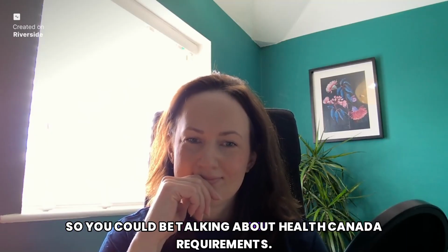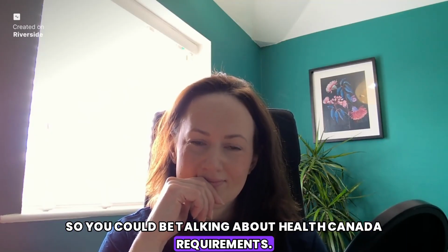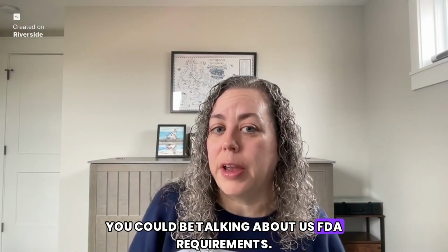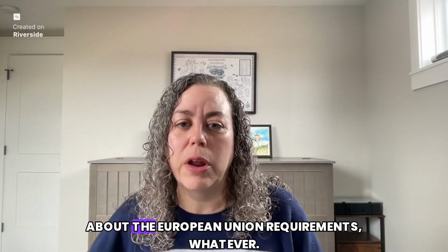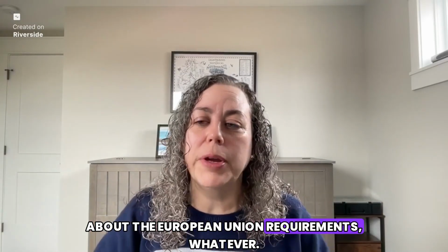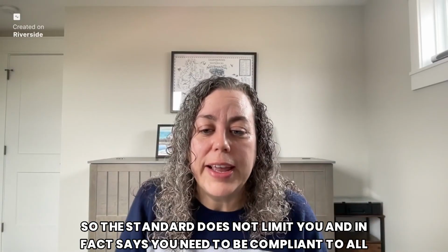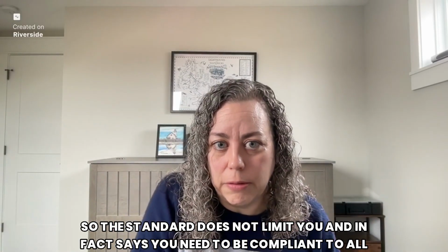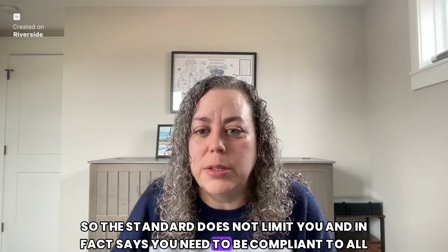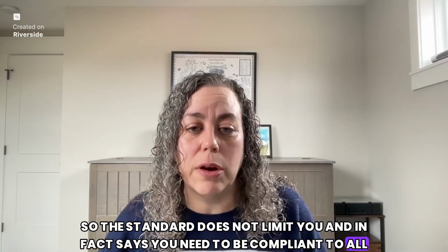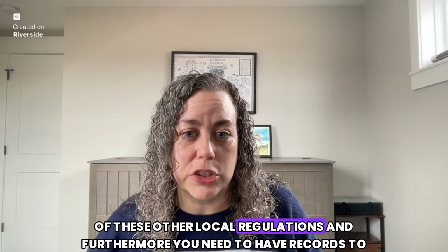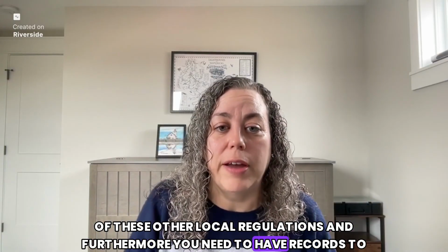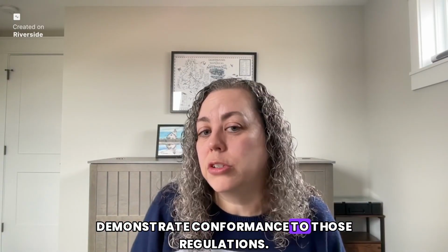So you could be talking about Health Canada requirements, you could be talking about US FDA requirements, you could be talking about the European Union requirements, whatever. So the standard does not limit you, and in fact says you need to be compliant to all of these other local regulations. And furthermore, you need to have records to demonstrate conformance to those regulations.